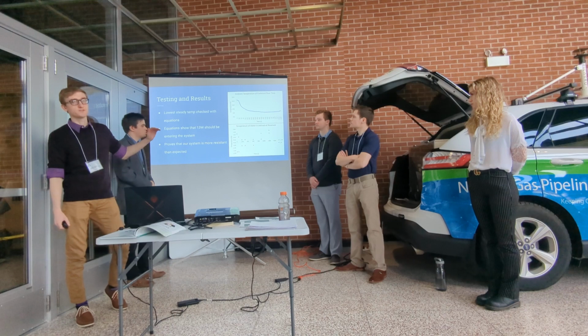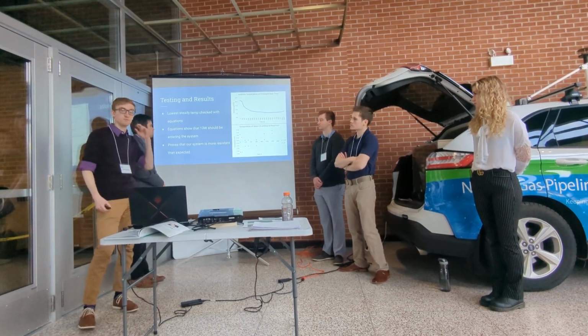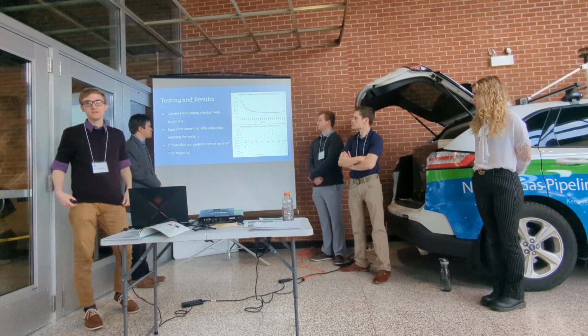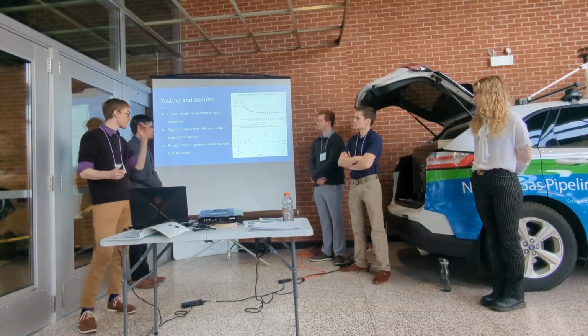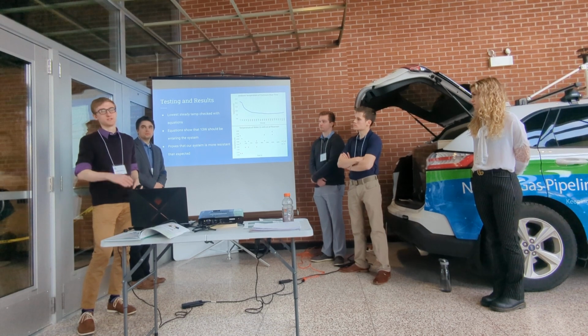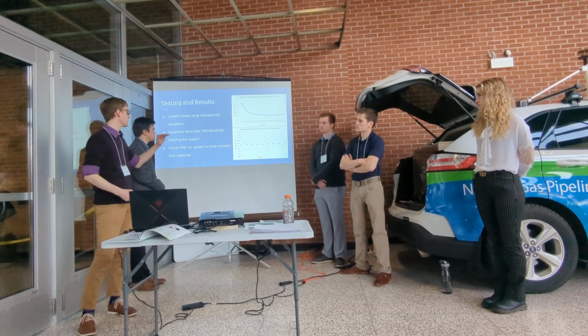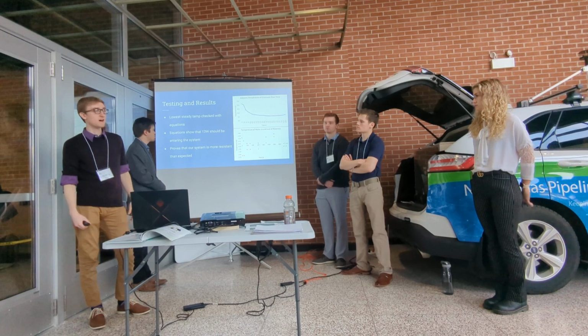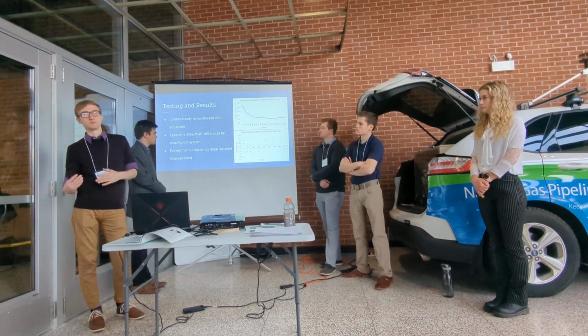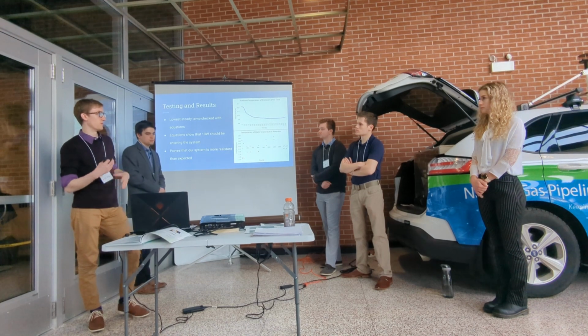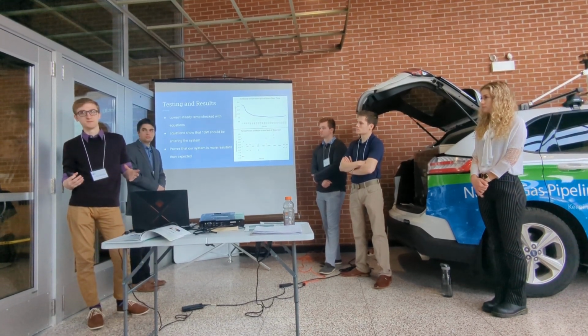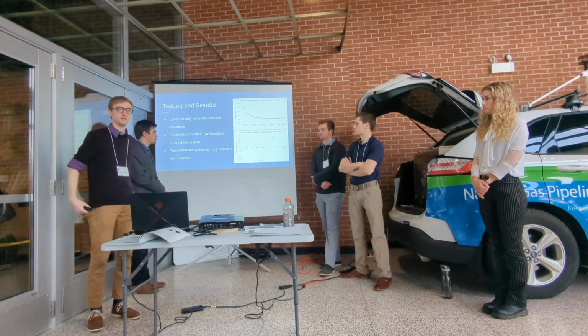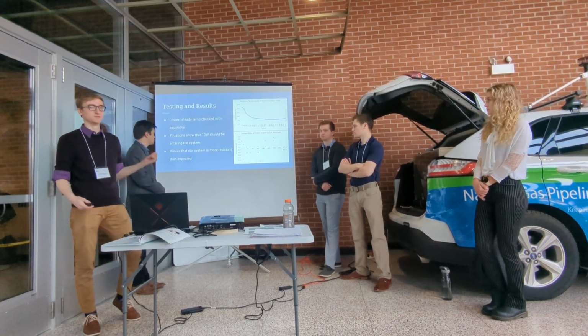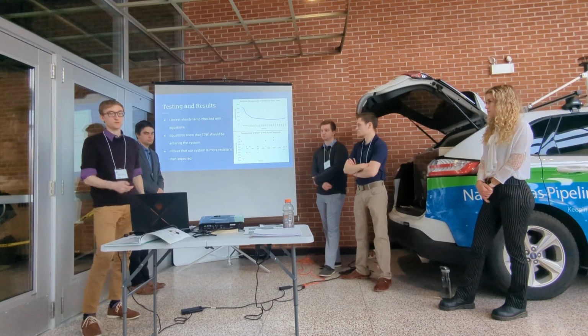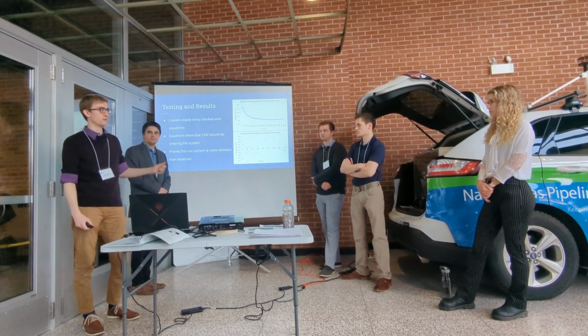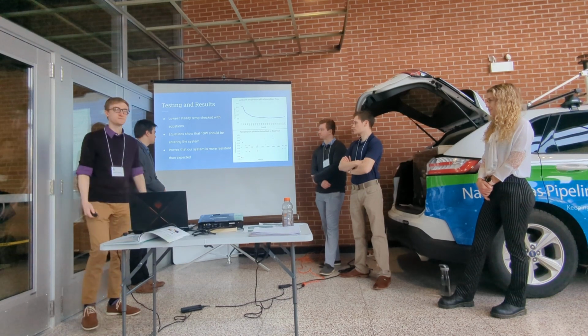With this steady state temperature, we used our earlier equations to determine the steady state temperature for our worst case scenario. That calculated temperature was actually higher than what we measured inside our box, which means either our cooling system delivers more cooling than we thought, or our box protects the system from more external heating than planned. So our system is performing better than we hoped, which proves it's viable.